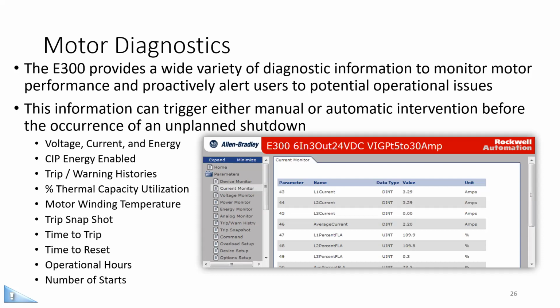So there's lots of useful information when the E300 trips or has a warning event. Trip or warning status words provide real-time information for the reason of the trip or warning event, which can be displayed in the SCADA system, such as on a panel view. The information can be used by maintenance personnel to help troubleshoot the motor issue. Up to 5 trip and warning events are logged into the trip and warning histories, which are stored in non-volatile memory.